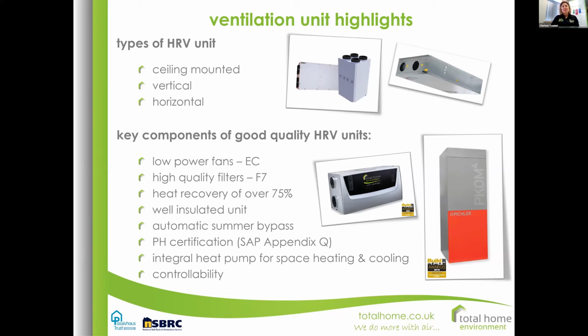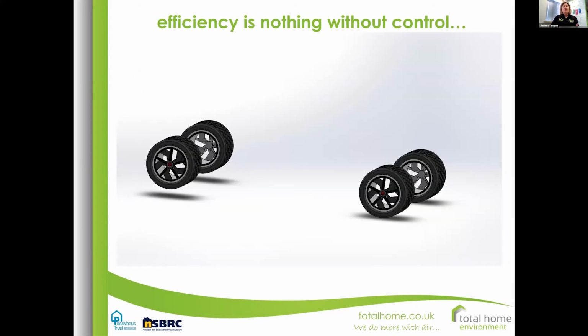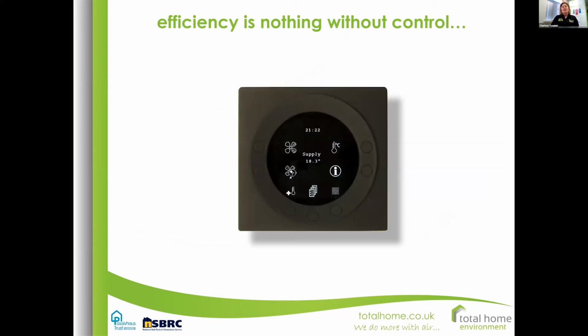And don't forget to look at the controllability. It's no good having a whiz of a unit if you've only got an on-off button and a boost switch. You know, control is everything when it comes to efficiency. And here on this particular controller, you can have your target temperature, you can have loads of information about what the weather's doing inside as well as out, and what your airflows are. Here, this is probably the most important thing, being able to be told when your filter needs to be checked, because if your unit is having to suck through a filter that is like a wall of dirt, it's going to be working harder, you're going to be using up more energy, and there's going to be more wear and tear. So that is absolutely paramount, to be able to be told when a filter needs to be checked.